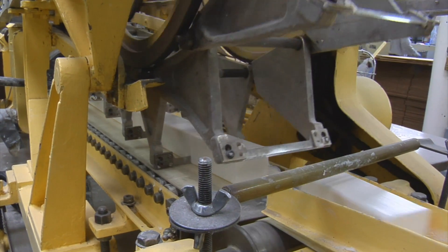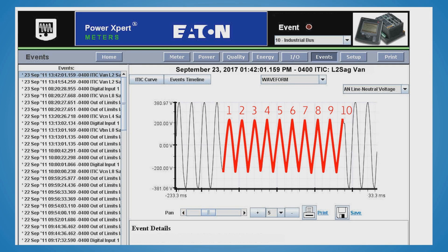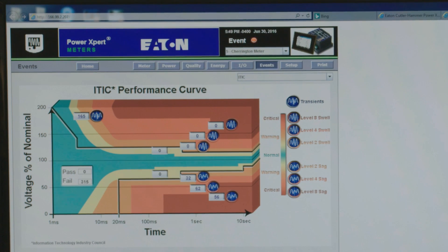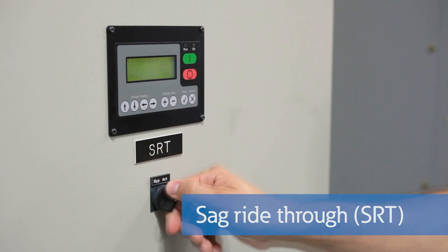Voltage sags are considered the most costly power quality event and the most common voltage variation, much more frequent than full interruptions on a typical power system. We've had many visitors tell us they've lost hundreds of thousands, even millions of dollars as a result of voltage sags. When evaluating voltage sag issues, identify the magnitude of the retained voltage, the duration of the event, and the number of phases affected. With enough statistical data, like the ITIC curve, you can feel comfortable that you understand the issue. Solutions range from small ride-through devices through large UPSs and everything in between.